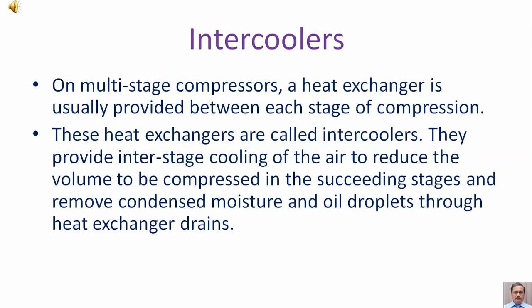On multi-stage compressors, a heat exchanger is usually provided between each stage of compression. These heat exchangers are called intercoolers. They provide inter-stage cooling of the air to reduce the volume to be compressed in the succeeding stages and remove condensed moisture and oil droplets through heat exchanger drains.